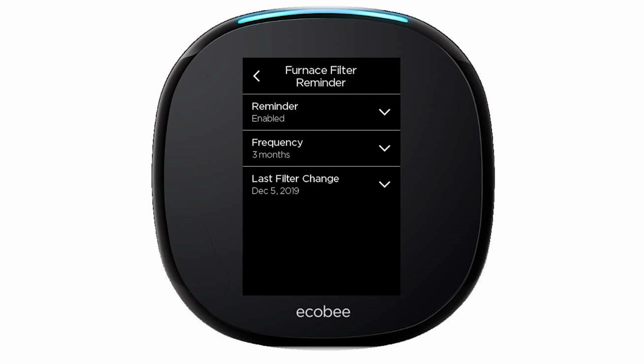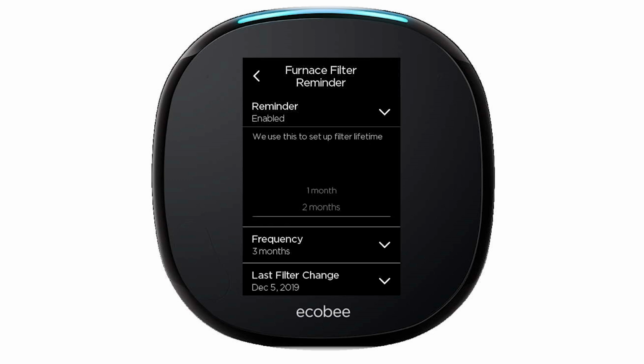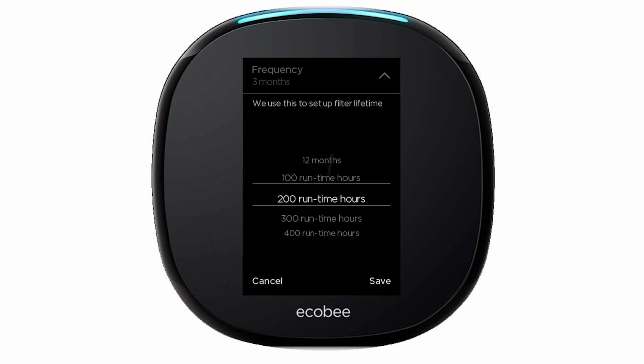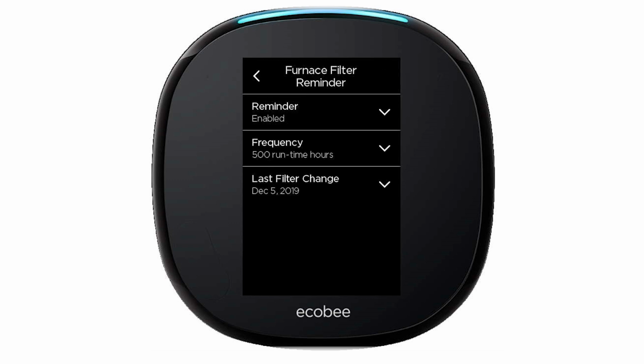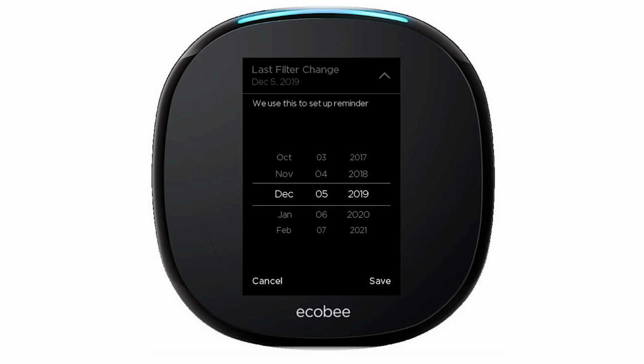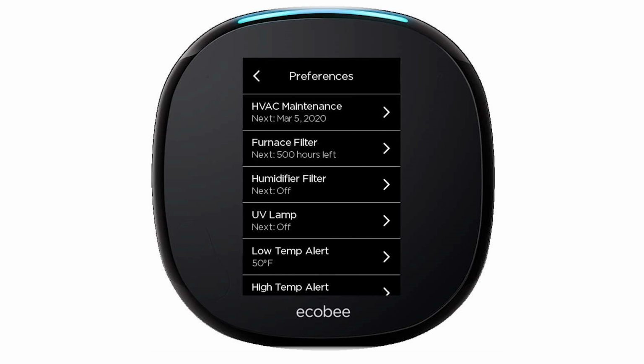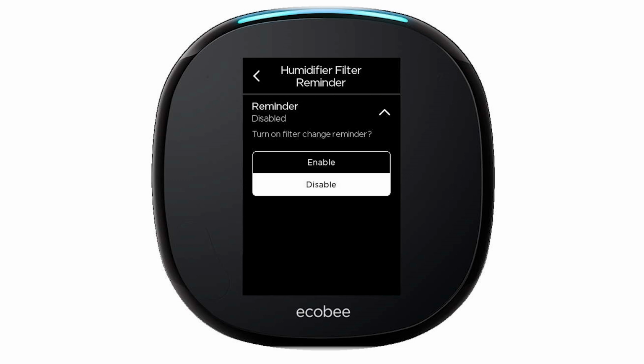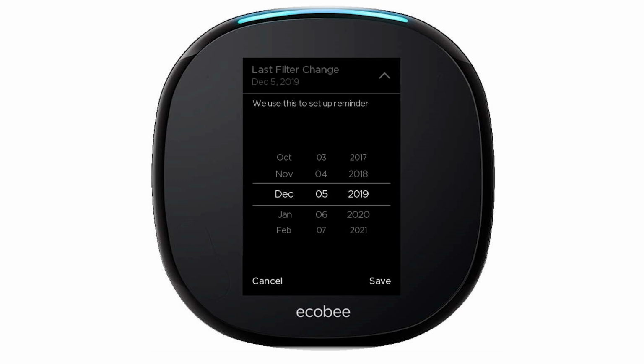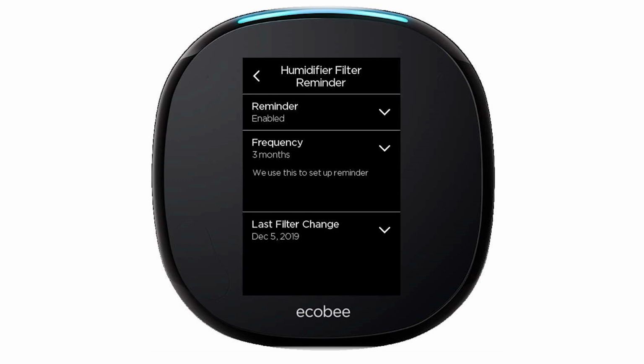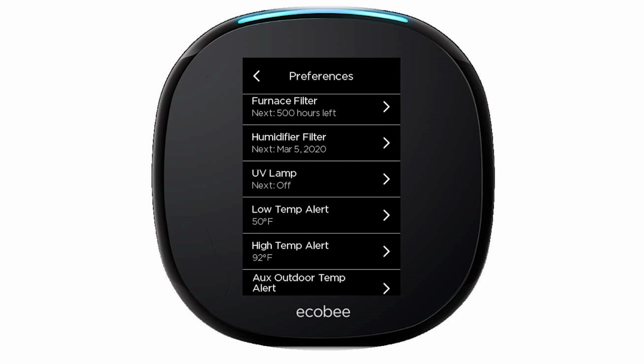Same with a furnace filter reminder. You can do frequency and time. You can also choose runtime hours. You could say every 500 hours the furnace runs, I want that filter changed, right? And that's going to push that reminder out to the homeowner, to the contractor, and let them know it's time for a new filter. So you can see just kind of going along here, you've got a reminder for an accessory. So humidifier, ventilator, dehumidifier, you can turn that on and you can set up those same preferences as far as frequency and your last service date.